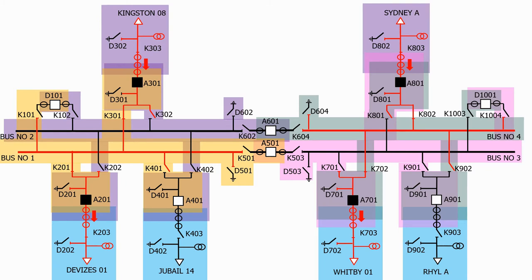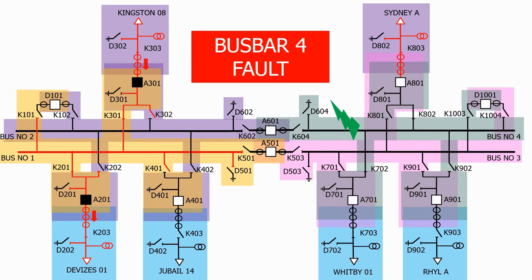Let's now add a fault on busbar number 4. Which protection zone will detect the fault? As we can see the fault is within the protection zone for busbar number 4. The busbar protection system operates, tripping all of the circuit breakers connected to the faulted busbar. We've now cleared the fault from the system.